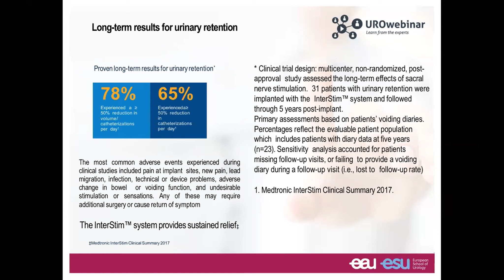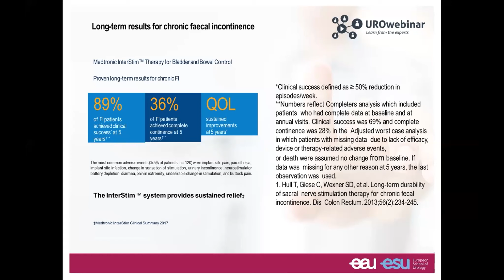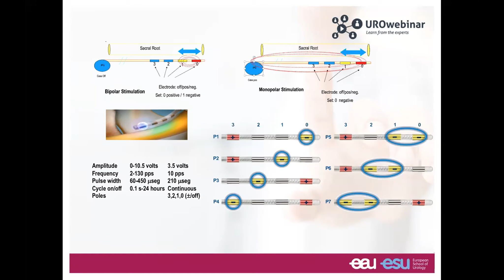And this is important because when we ask patients in our clinic, complaining of lower urinary tract symptoms, about fecal incontinence, we realize that a high percentage of patients, let's say even more than half, might have some kind of fecal incontinence or bowel disorder, which is important to take into account at the time of choosing therapy. Programming of the device is rather easy. The device comes with a setting of 7 different programs. Although we can change this, we can even do bipolar or monopolar stimulation. We always prefer bipolar because the consumption of the battery is much higher with monopolar, and then the life of the battery is shorter.